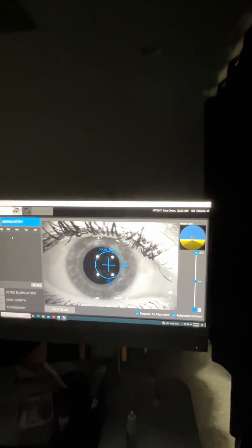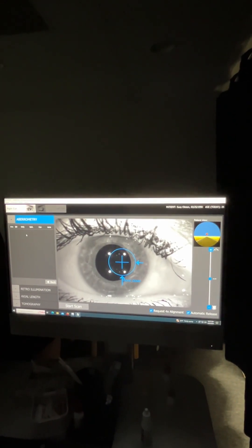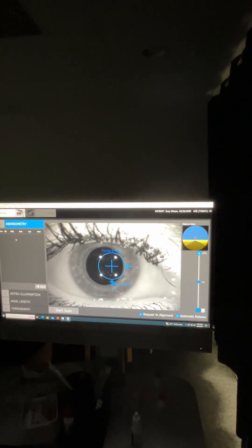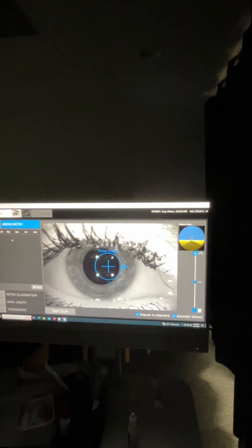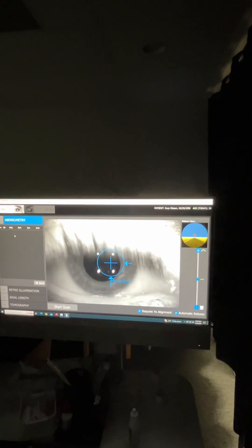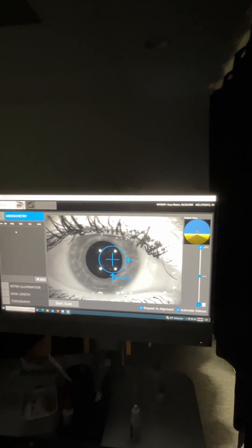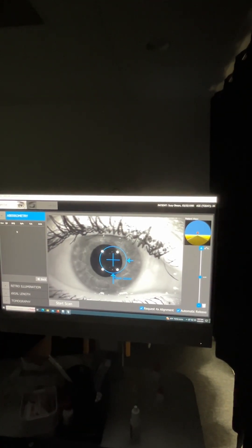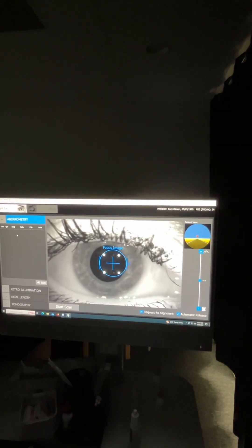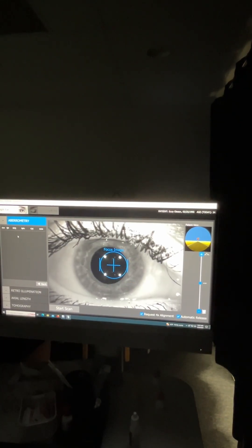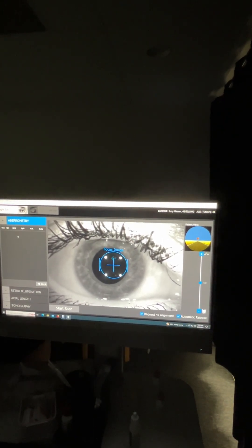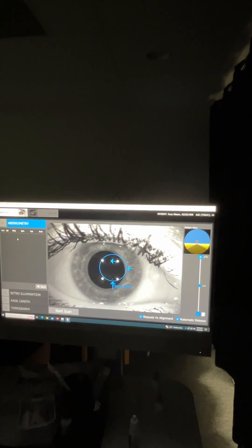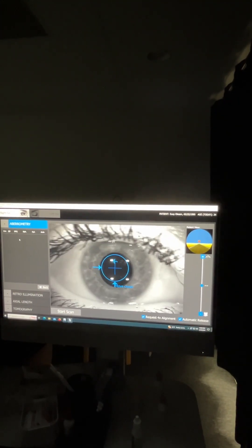This part I believe is important. You need to verbalize to the patient that the hot air balloon will be blurry at times. It'll be in focus and then it'll go out of focus and then it'll do that typically multiple times. It's important to let them know that they can let it be blurry if you want to get an accurate refraction. So this is similar to like a typical auto refractor where if the patient is trying to keep the hot air balloon in focus, then it's going to give you a significant over minus.